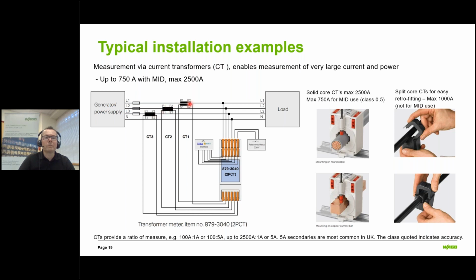On a three phase system, you'll see a CT on each phase. So the meter can report the current in each phase. And of course it can also report the power, which is essentially a mathematical equation of the voltage times the current, taking into account power factor as well, of course. And of course these CTs can go up to 2500 amps from WAGO if it's a solid core. The split core is limited to 1000 amp rated.